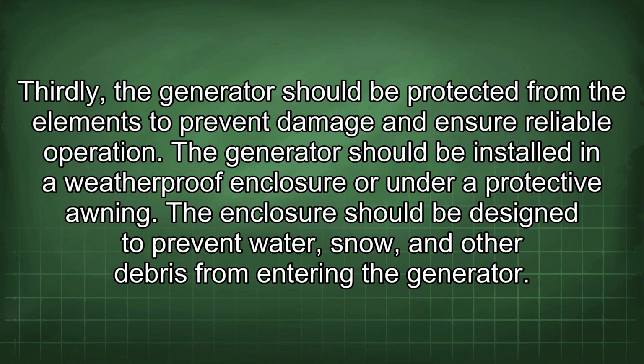Thirdly, the generator should be protected from the elements to prevent damage and ensure reliable operation. The generator should be installed in a weatherproof enclosure or under a protective awning. The enclosure should be designed to prevent water, snow, and other debris from entering the generator.